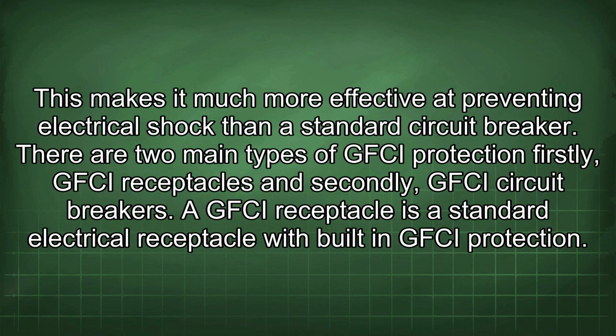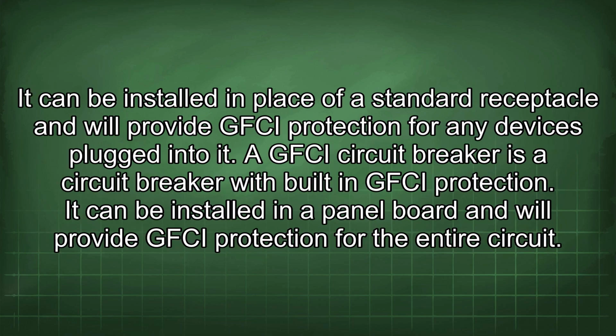This makes it much more effective at preventing electrical shock than a standard circuit breaker. There are two main types of GFCI protection: firstly, GFCI receptacles, and secondly, GFCI circuit breakers. A GFCI receptacle is a standard electrical receptacle with built-in GFCI protection. It can be installed in place of a standard receptacle and will provide GFCI protection for any devices plugged into it. A GFCI circuit breaker is a circuit breaker with built-in GFCI protection.